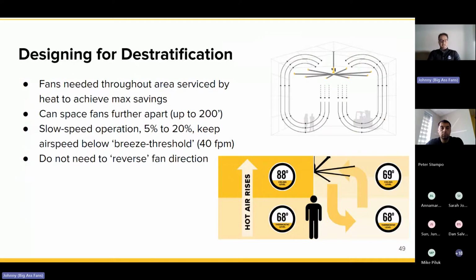You want to make sure you're mixing the entire air volume as opposed to creating high elevated air speeds directed at people. So with destratification, you're often going to run the fan slower. In the winter months, you definitely don't want a breeze. All of these types of products would have a variable speed drive, if not sensors or temperature sensors in the control to adjust speed accordingly. So they're very intuitive and intelligent when it comes to not creating adverse effects in the winter, but mixing the air and achieving what you need, which is that temperature homogenization.